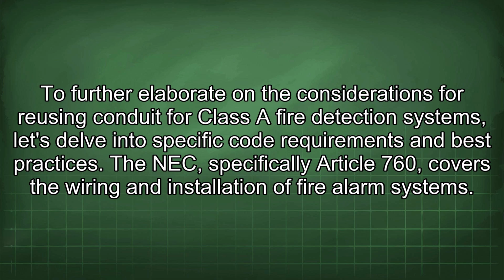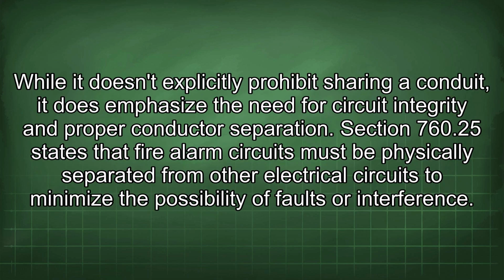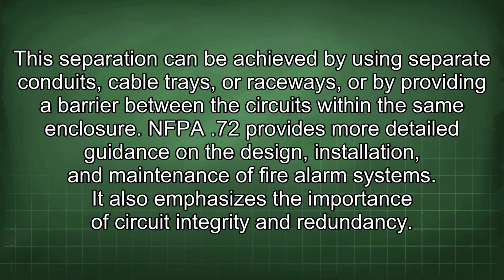The NEC, specifically Article 760, covers the wiring and installation of fire alarm systems. While it doesn't explicitly prohibit sharing a conduit, it does emphasize the need for circuit integrity and proper conductor separation. Section 760.25 states that fire alarm circuits must be physically separated from other electrical circuits to minimize the possibility of faults or interference. This separation can be achieved by using separate conduits, cable trays, or raceways, or by providing a barrier between the circuits within the same enclosure.